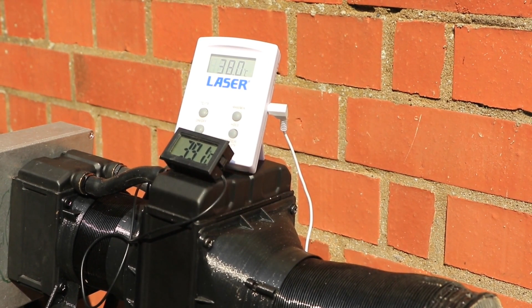What I've done is laid the probe down inside the exhaust to see if that made a difference, and it did come up slightly, but it seems the prevailing wind is actually coming this way and blowing up the end here, which is just enough to cool the probe and make a difference. It's kind of good that these temperatures are similar, because it shows that we are reclaiming almost all of the energy available.